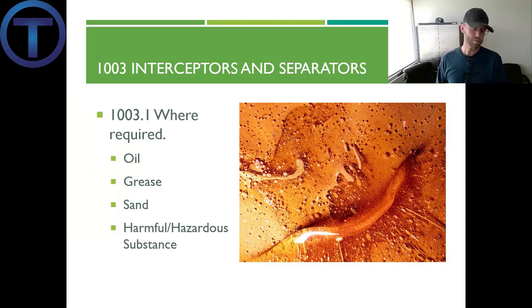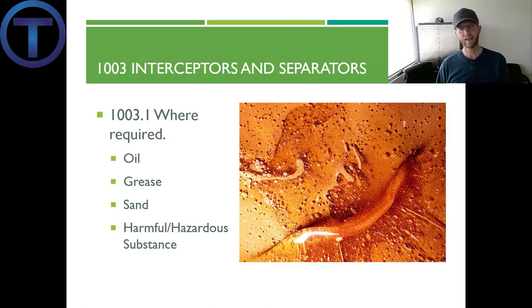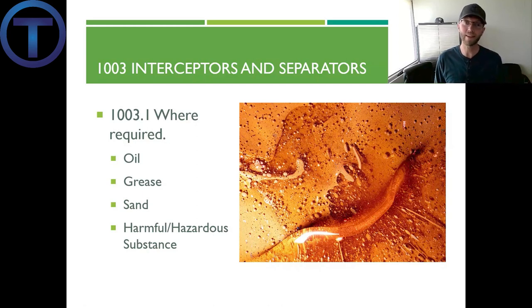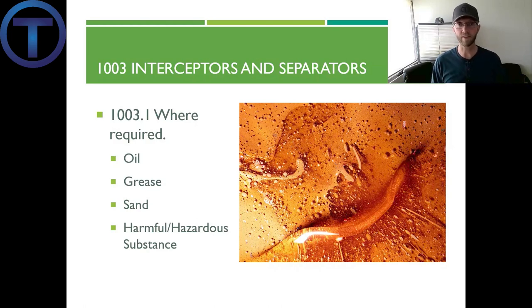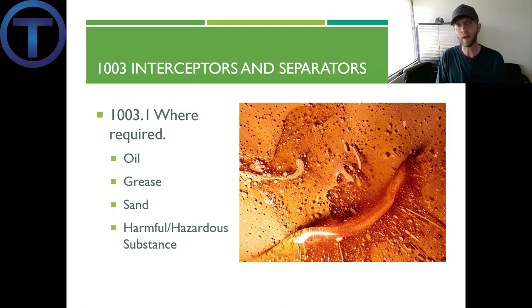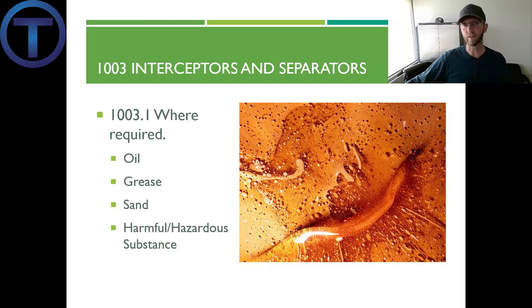Section 1003.1 talks about where interceptors are required. Where do you think you would need a separator? First, we might ask: what are we trying to separate? It gives us a list of things you should not be putting down the drain, which includes oil, grease, sand, or other harmful or hazardous substances — anything that could damage the sewer system or the environment. We have to find some way to separate those out before the fluid goes down the normal sanitary sewer.